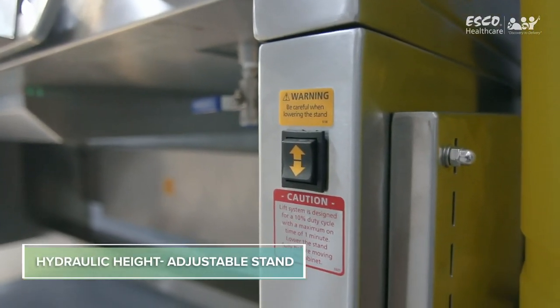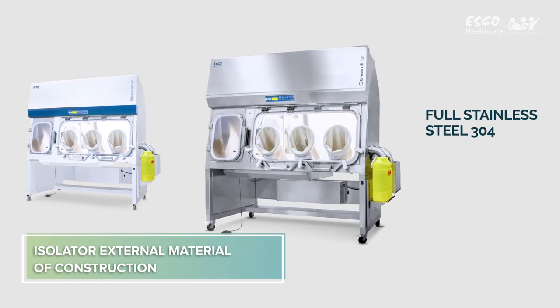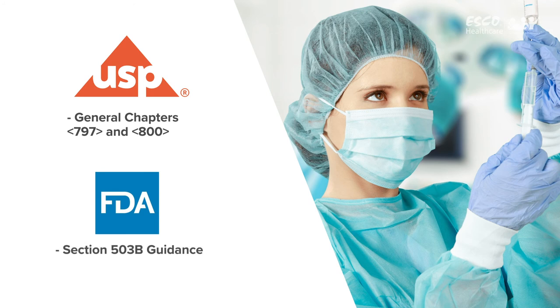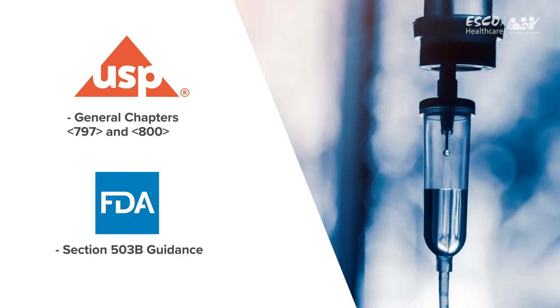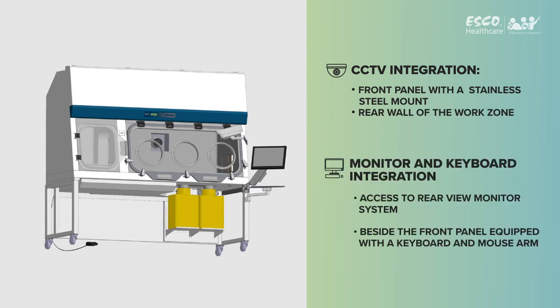Accessories and options include a sharps disposal system located at the bottom of the work zone, beside the work zone, or inside the work zone. A hydraulic height-adjustable stand is available as an option. External material of construction options include electro-galvanized steel with Isocide antimicrobial powder coating or full stainless steel 304. United States Pharmacopeia General Chapters 797 and 800, together with FDA Section 503B guidance, state the need for medical surveillance and proper documentation of standard operating procedures surrounding activities for sterile pharmaceutical preparations.